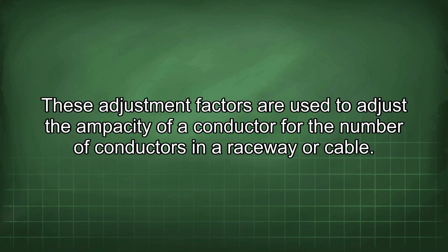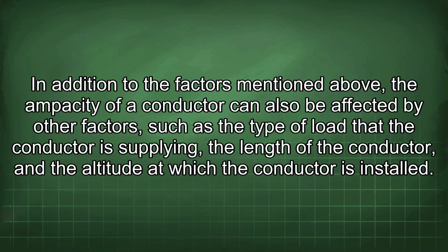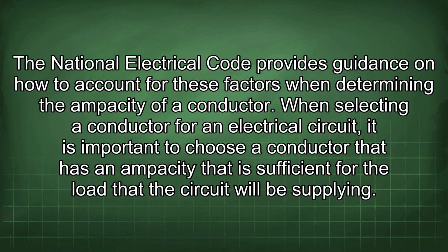In addition to the factors mentioned above, the ampacity of a conductor can also be affected by other factors, such as the type of load that the conductor is supplying, the length of the conductor, and the altitude at which the conductor is installed. The National Electrical Code provides guidance on how to account for these factors when determining the ampacity of a conductor.